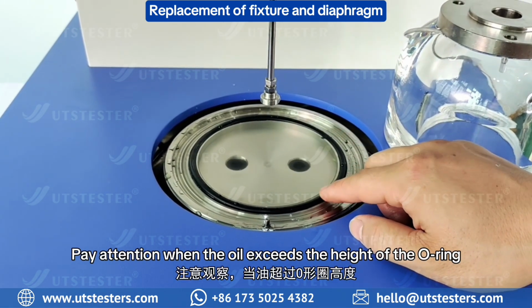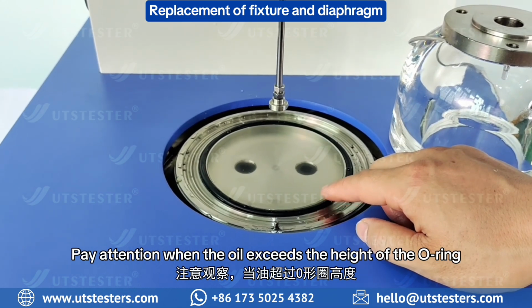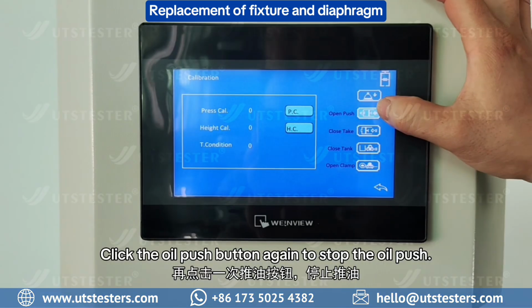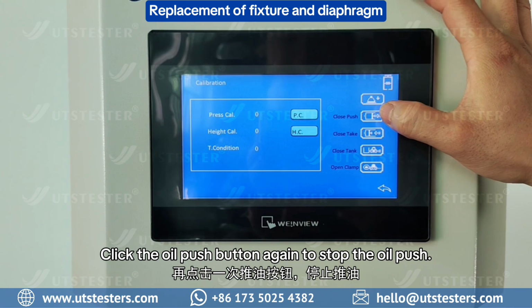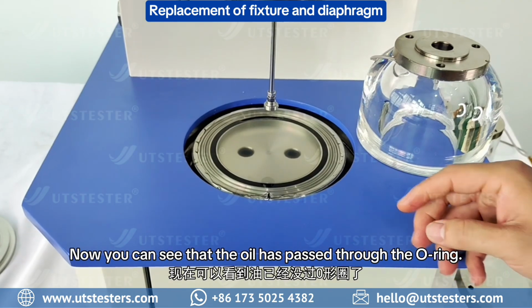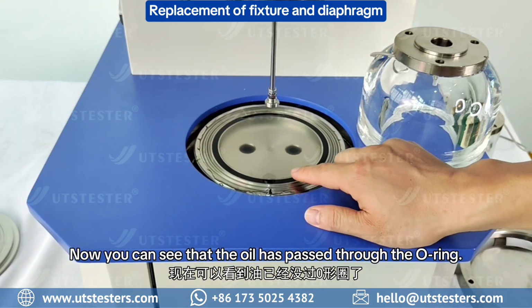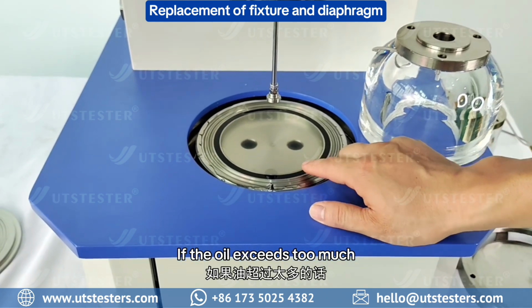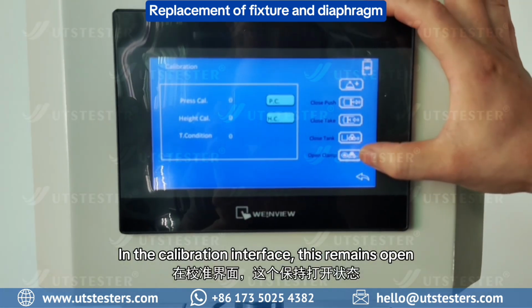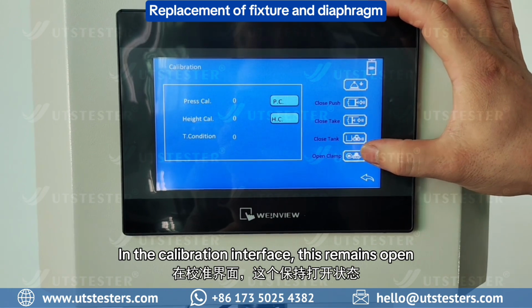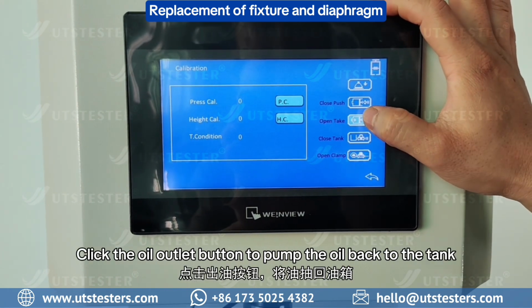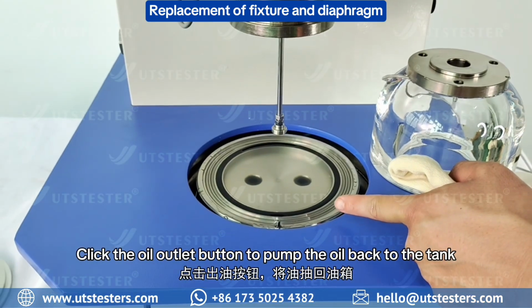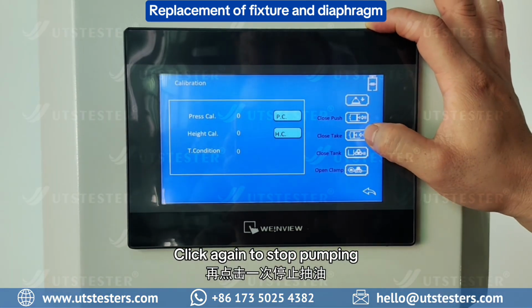Pay attention when the oil exceeds the height of the O-ring. Click the oil push button again to stop the oil push. Now you can see that the oil has passed through the O-ring. If the oil exceeds too much, in the calibration interface, this remains open. Click the oil outlet button to pump the oil back to the tank. Click again to stop pumping.